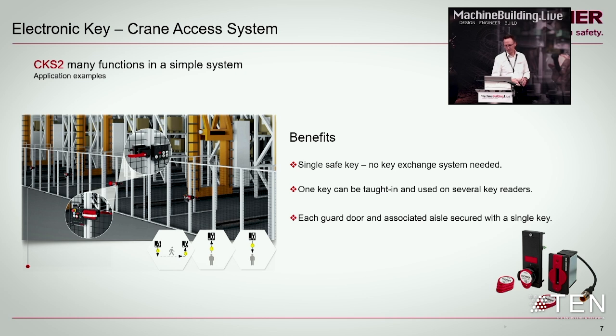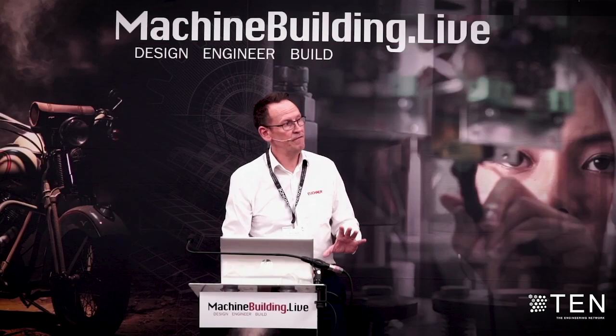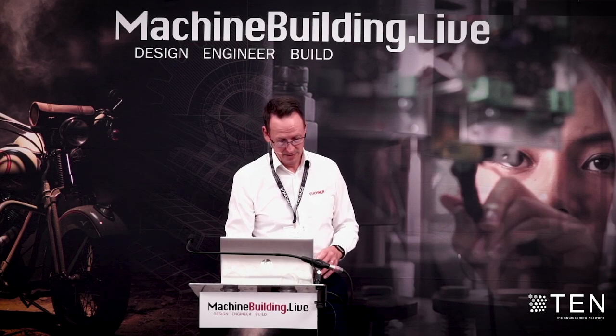It's in an electronic environment now. We can do one key, which can have many functions associated with it, such as key transfer. And each guard door and associated aisles can be accessed with a single key. There's a standard, EN 528, for aisle cranes that has a specific requirement about the access requests, the need to lock the door behind, put the key into a crane, and do the manipulation of the crane in an aisle safely. So we can use that automation to configure that system really quickly and simply.